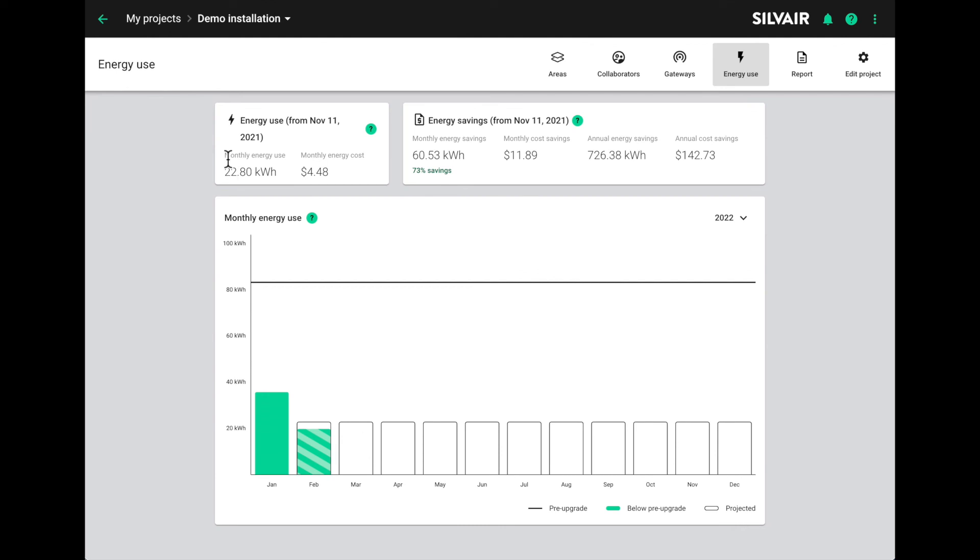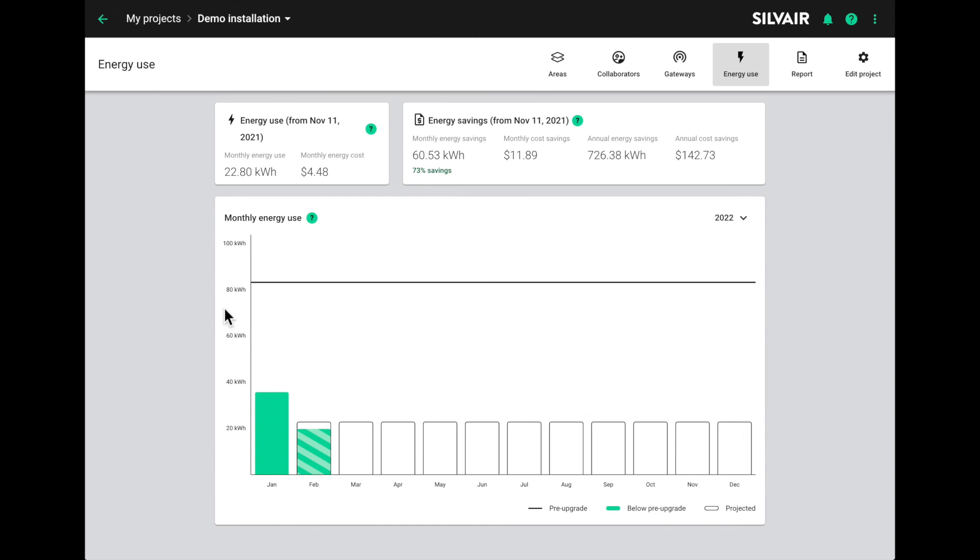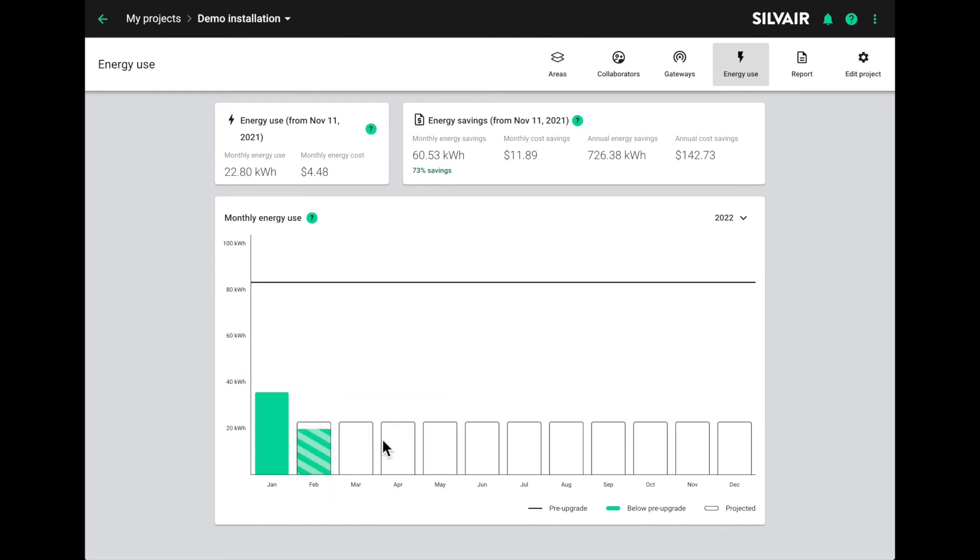At the top of the page, we see the energy consumption in the current month together with the cost of that energy based on the average price we entered in the project settings. We also see the savings compared to the previous installation, both in terms of kilowatt hours saved and money saved. We see a bar chart showing the monthly monitored energy use and how this compares to the baseline or the average monthly pre upgrade energy use for the project. We also see a projection of how much energy will be used over the year based on the data available.